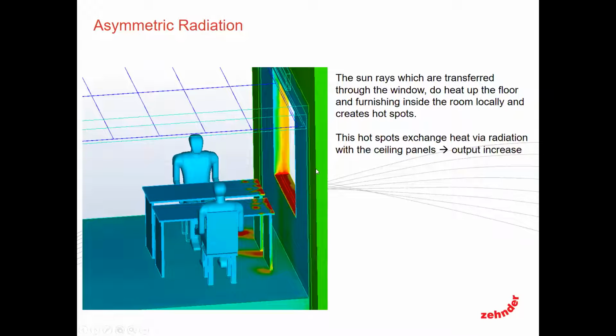We know that during direct solar sunlight time, you're going to get light that passes through the glass facade and starts warming up certain areas within the space itself. So if you have a large glass facade, when that direct solar sunlight comes into the space, it warms up the floor, the windowsill, the occupant, or the table. What's happening? You're driving up the surface temperature on that object, and you still have the chilled surface. As that chilled surface temperature stays the same, let's just call it 60, and this temperature starts going up, the delta T between these two surfaces increases. As that delta T increases, you get more BTUs per square foot.